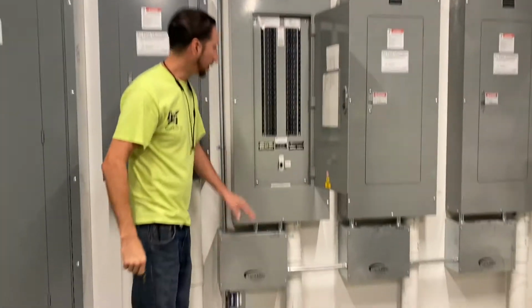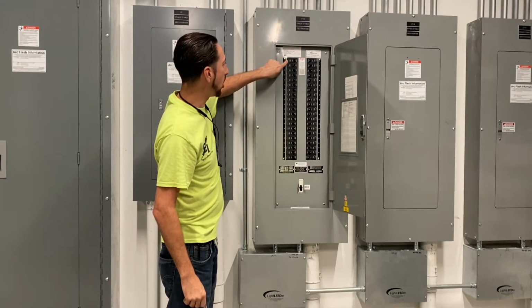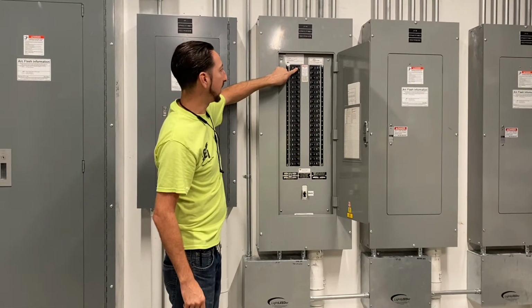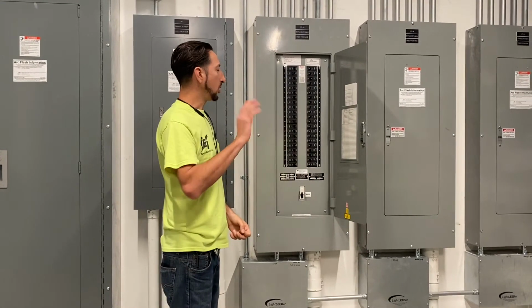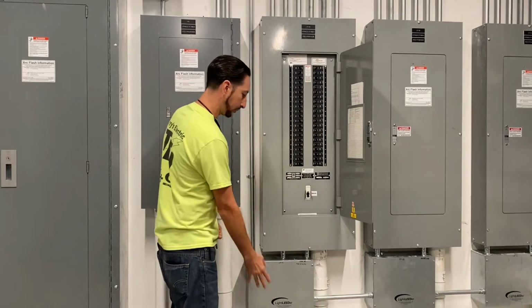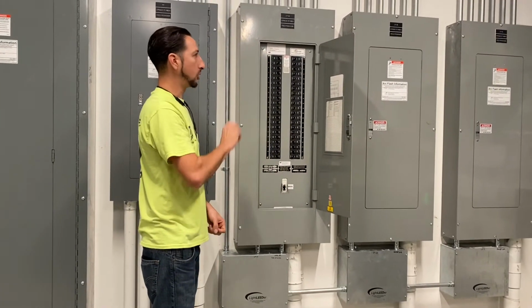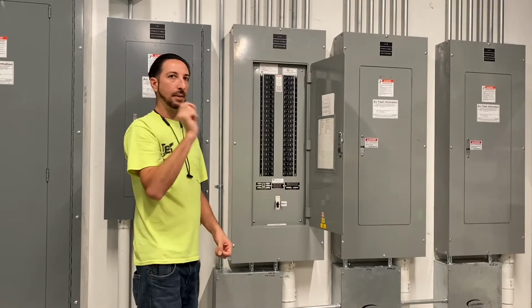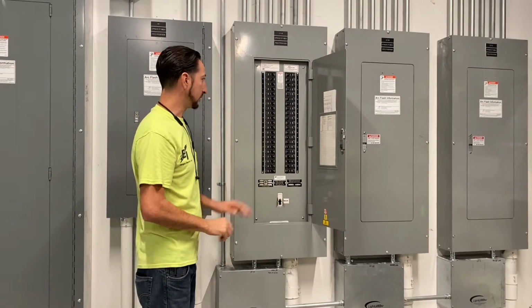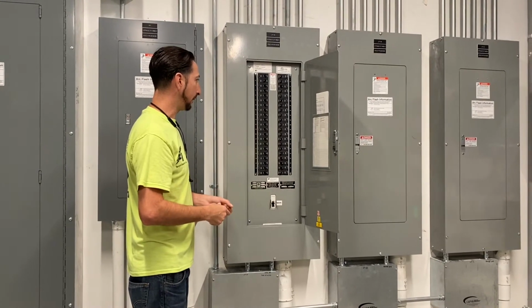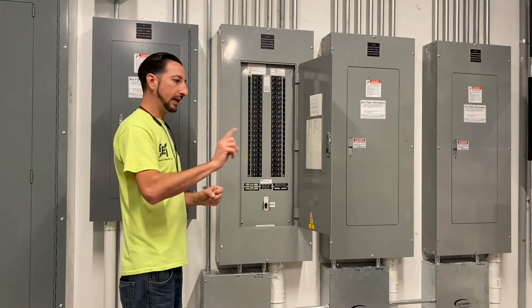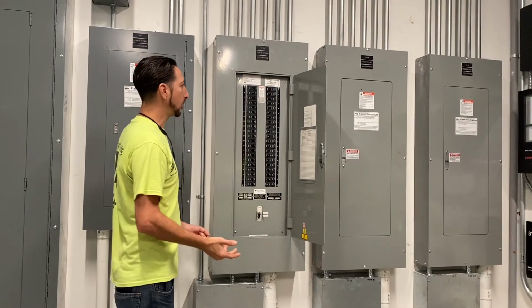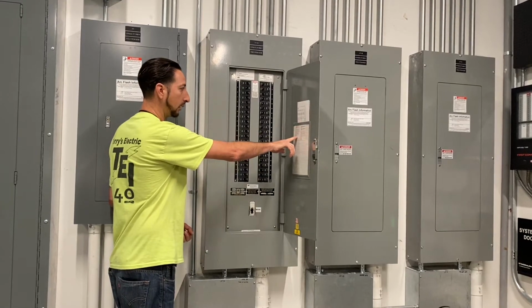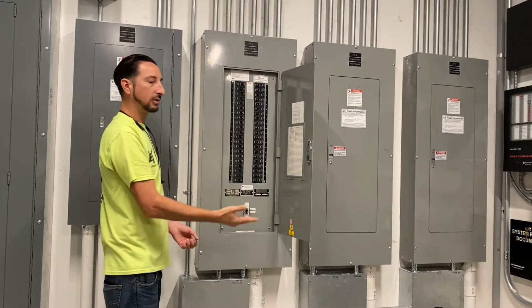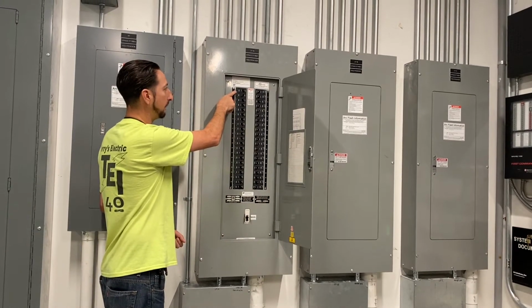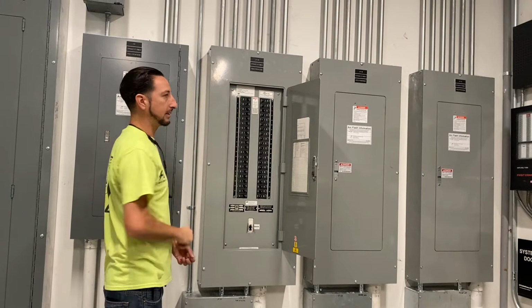So this processor tells this little relay right here to turn on and off as long as the breaker is energized. So when you go to a switch station and it talks to the processor and tells circuit number 1 to turn the lights on and off, this will toggle automatically. So all that function is done right here at the panel. So if there's ever a circuit that is not functioning off of the switch station, you could come to the panel, you could read the schedule here, find the area that it has lost lighting, and then you could check to see if the relay is in the on state.